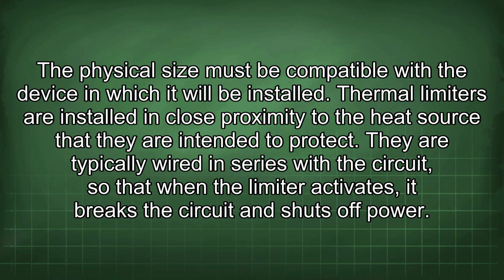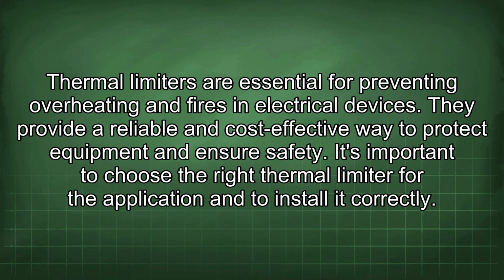Thermal limiters are installed in close proximity to the heat source that they are intended to protect. They are typically wired in series with the circuit so that when the limiter activates, it breaks the circuit and shuts off power. Thermal limiters are essential for preventing overheating and fires in electrical devices. They provide a reliable and cost-effective way to protect equipment and ensure safety. It's important to choose the right thermal limiter for the application and to install it correctly.